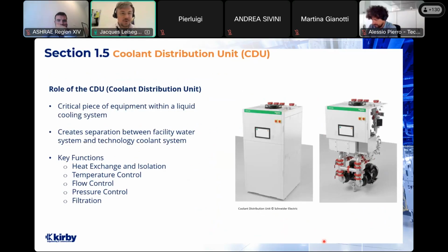All right, the coolant distribution unit. The coolant distribution unit is a critical piece of equipment within a liquid-cooled system. There are four connections to it. You have two connections for your facility water loop, your standard chilled water loop, and then two connections for your technology water loop. Within the CDU, you have a pump set which manages the flow control and the pressure control to your technology system. There's a heat exchanger within the CDU that provides the hydraulic separation between your facility water loop and your technology water loop.